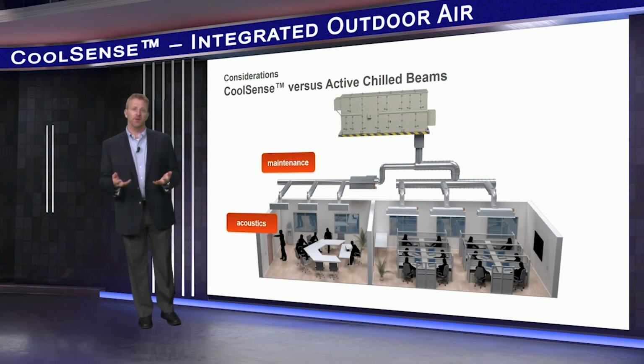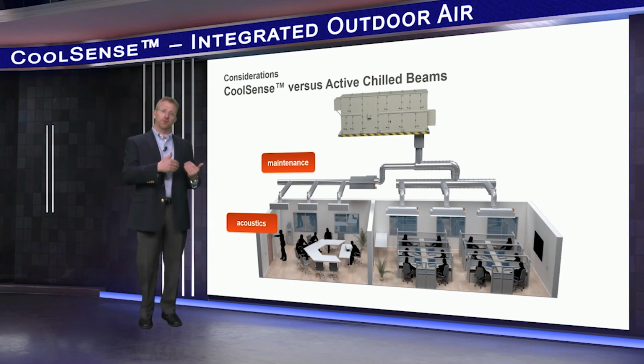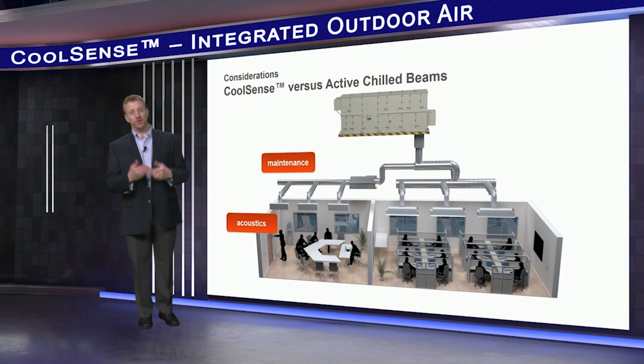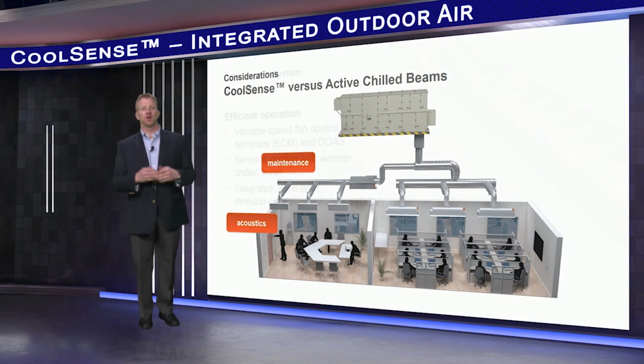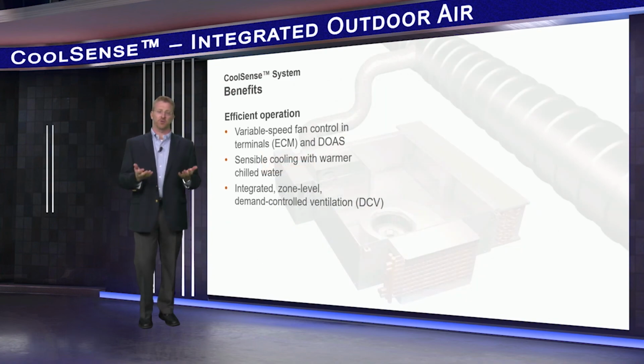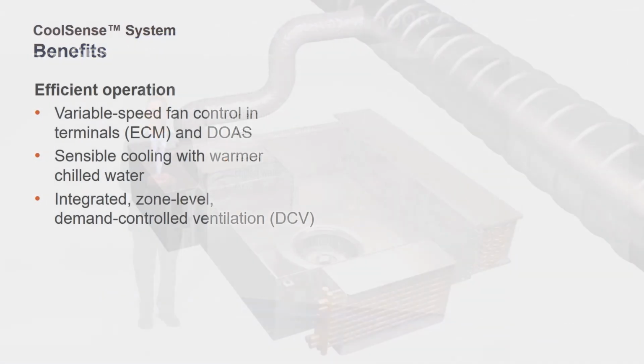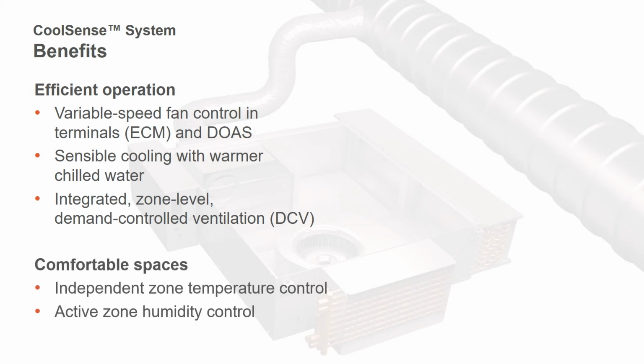For the school example, this would allow maintenance staff to change the filters without disrupting class, and the noise would more easily be attenuated. So let's review the benefits of Trane's new CoolSense system. It offers efficiency advantages through the variable speed ECM fans, dual temperature chilled water plant, and minimizing of ventilation air, all while maintaining space comfort through individual zone control of both temperature and humidity.